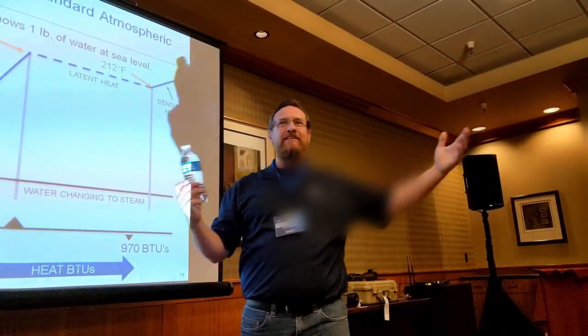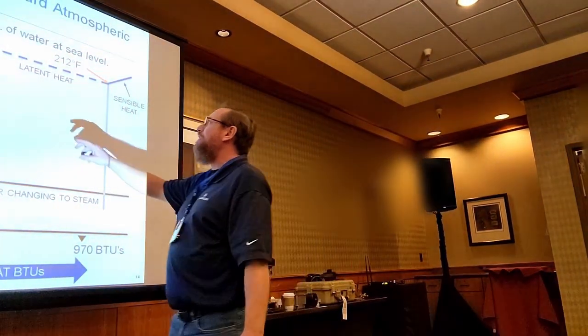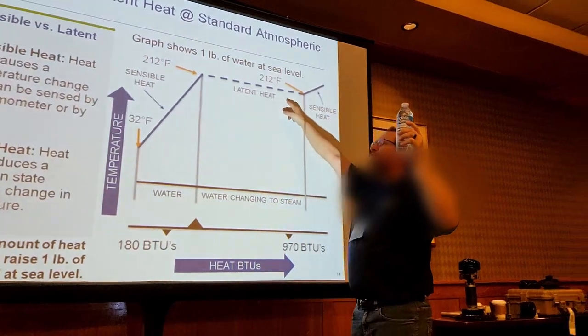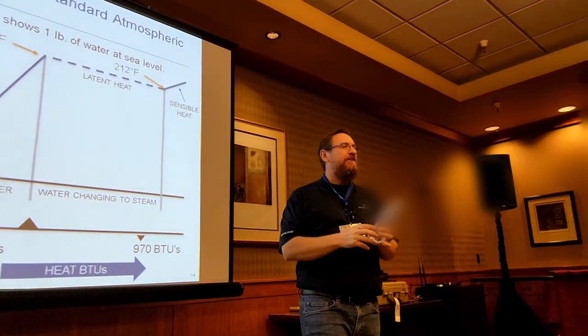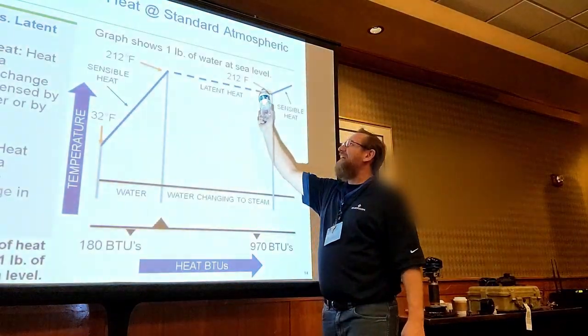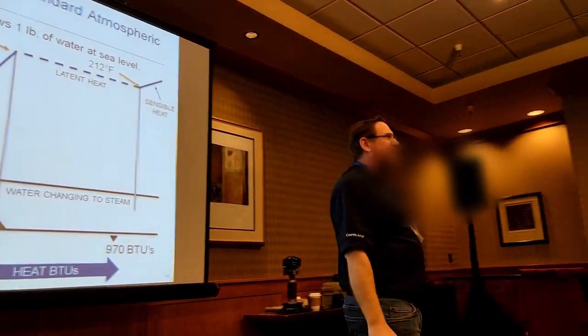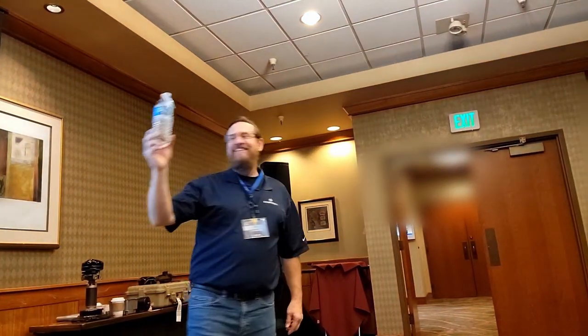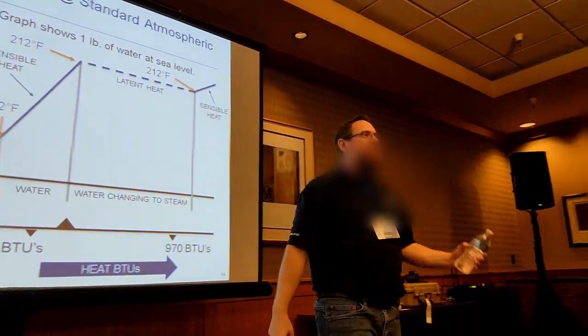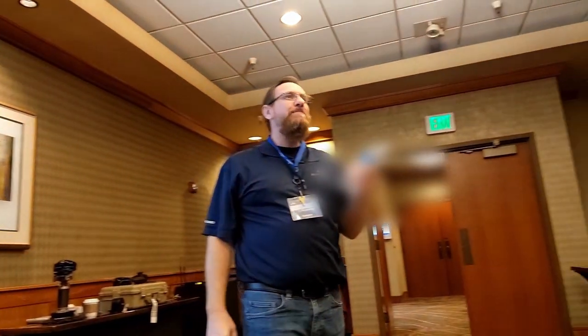32 liquid, 212 liquid. Now, if we made this change state from a liquid to a vapor at the same temperature — 970 BTUs of heat energy. Now, if 180 was significant, what about 970? That's latent heat. Sensible heat is a change in temperature, but latent heat — it didn't change temperature at all. 970 BTUs.